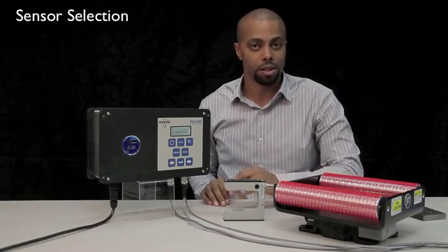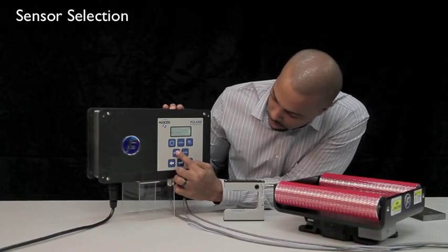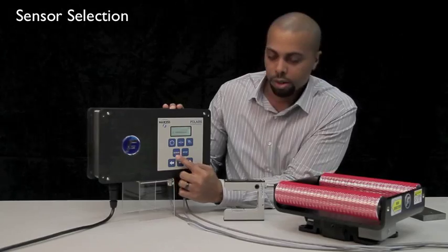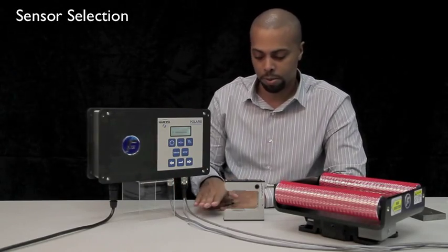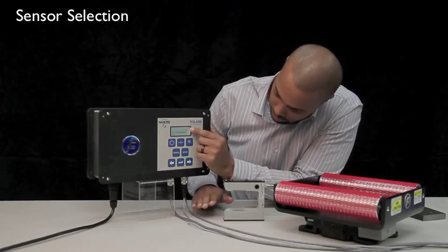To select the correct sensor, press your sensor button repeatedly until the correct sensor is displayed. You can verify you have the correct sensor selected by moving a piece of material in and out of your sensor and monitoring the bar graph on the display.